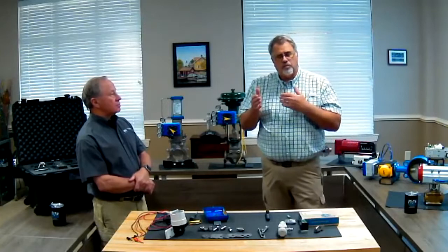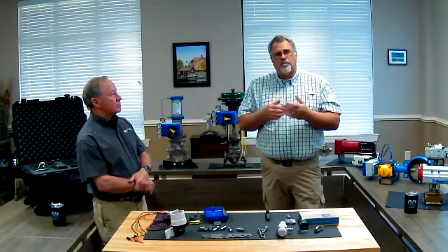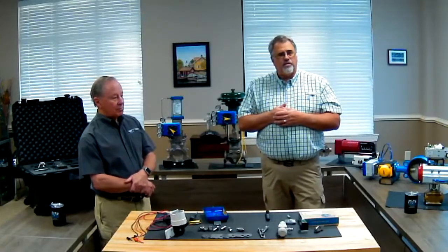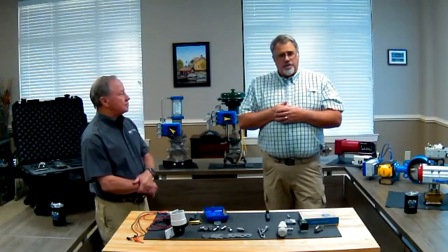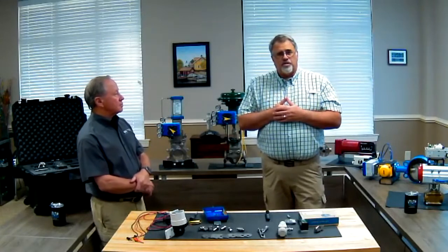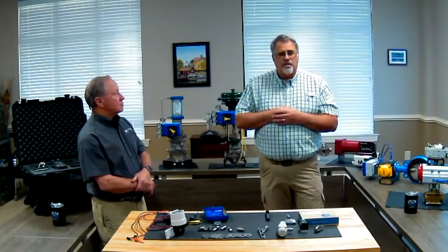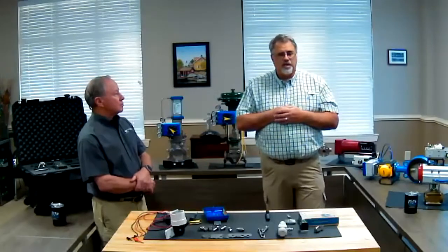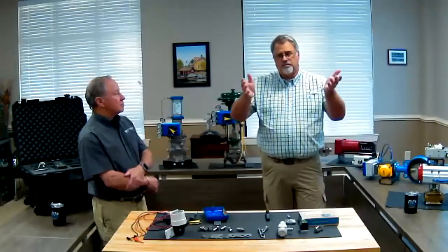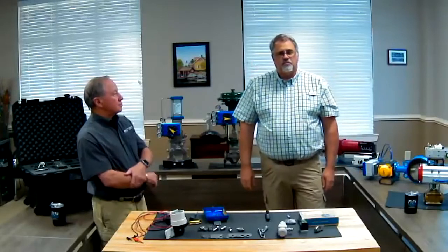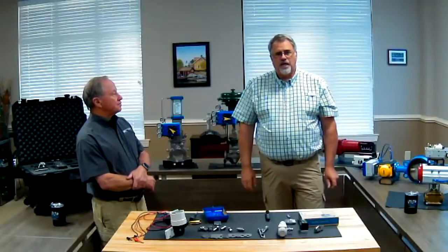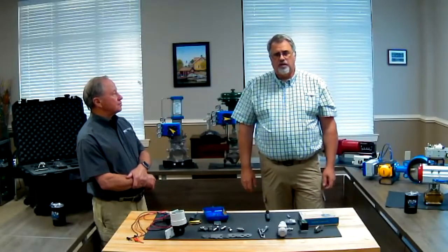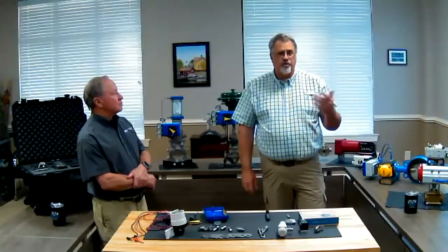So you need to be able to go from closed to open to closed again. The valve's going to be offline for a little bit, but if they're replacing an old obsolete positioner with one of our products, they're going to be ready to do that. We regularly do this. About two weeks ago, I did this on some 12-inch 2500 class globe valves at a gas storage facility, and we did it in place, outdoors, and each one took about an hour and a half. At least 50% of that time was removing the old products.